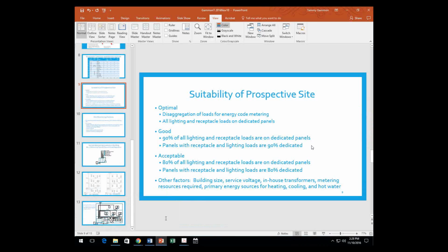I was talking about the band on a little differently, like you're metering your main service into a building, and say you've got a 500 kVA transformer feeding it. But if you only have a 300 kVA demand, you're allowed to multiply that by 1.25. So I think in that case it would be 375, and you would still be allowed to add 125 kVA to that service.